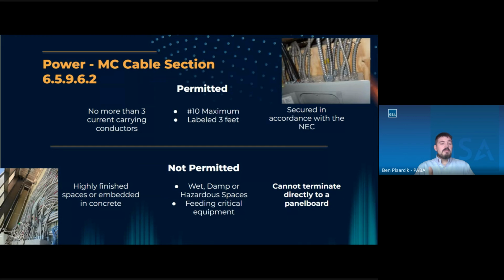MC cable, very hot topic, common topic that comes up. I have not listed everything from P100 here. I would encourage you to go to that section number if you're not familiar with it and read through it, but no more than three current carrying conductors. Number 10 maximum, labeled every 3 feet, secured in accordance with the NEC. We do not use it in highly finished spaces or embedded in concrete. We also don't use it in wet, damp, or hazardous spaces or feeding critical equipment.